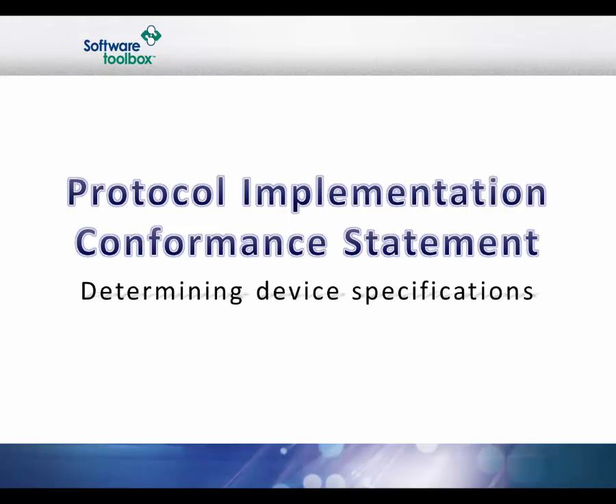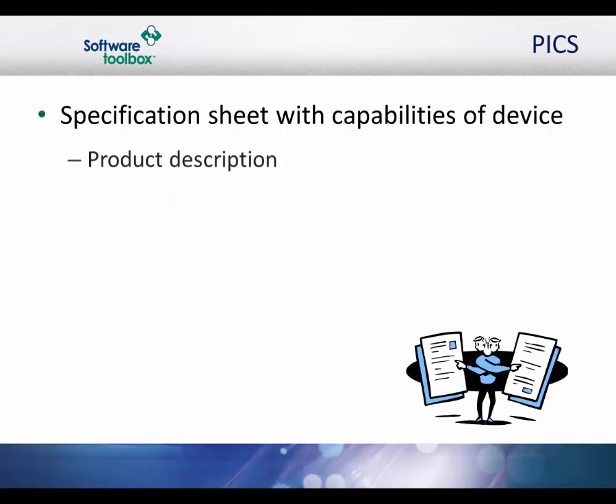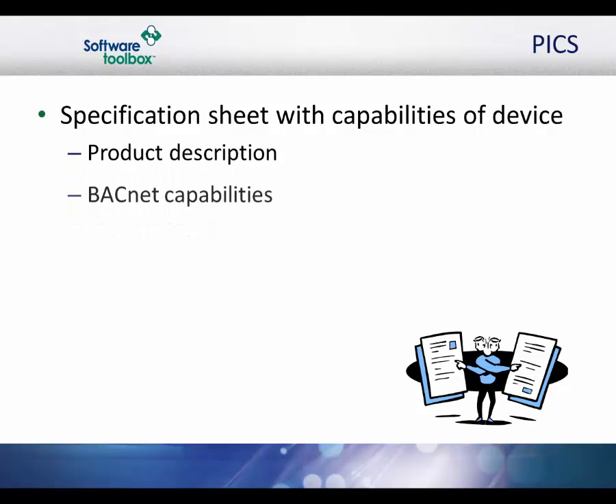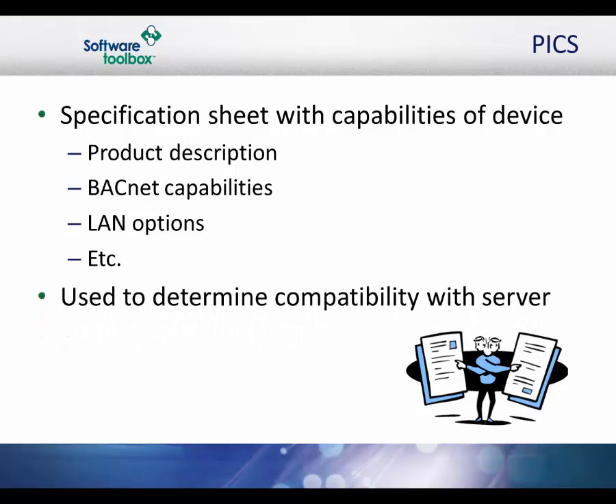Every BACnet device is required to have a PICS, or Protocol Implementation Conformance Statement. It is basically a BACnet specification sheet containing a list of a device's BACnet capabilities. It contains a general product description, details of the product's BACnet capabilities, the LAN options available, and a few other items relating to character sets and special functionality. A PICS is the first place to look to determine if a BACnet device is compatible with a particular server.